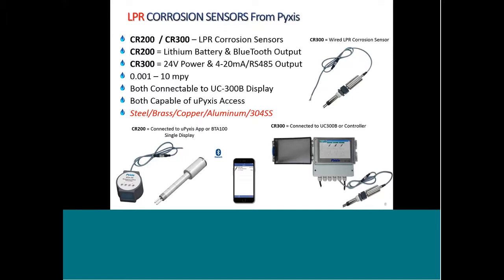So that in and of itself differentiates the Pyxis technology. Most, you know, with the Rohrback, you do need to purchase their recorder. There are multiple interfaces along the way that pigeonhole the customer to using intermediate devices and/or Rohrback devices to record corrosion. With the CR300, that's not a concern. You can wire this to a conventional controller. All the transducer and algorithm information is built into the probe itself, so it is simply a probe purchase.